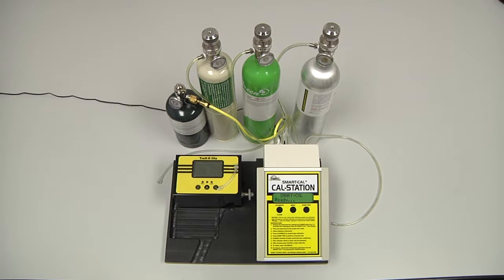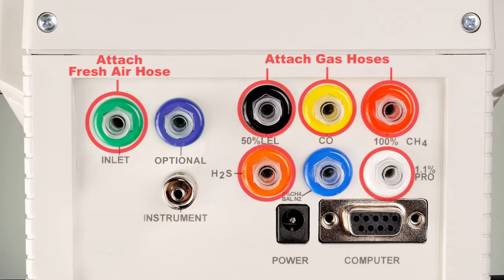This is a 4-gas instrument set for natural gas, so we will need a combination bottle of 2.5% by volume methane and 100 parts per million CO, air balance, attached to both the black and yellow inlets of the cal station through a Y adapter, a bottle of 100% by volume methane, attached to the red inlet, a bottle of 25 parts per million hydrogen sulfide, attached to the orange inlet, and if we were calibrating for propane, a bottle of 1.1% by volume propane, air balance, attached to the white inlet.